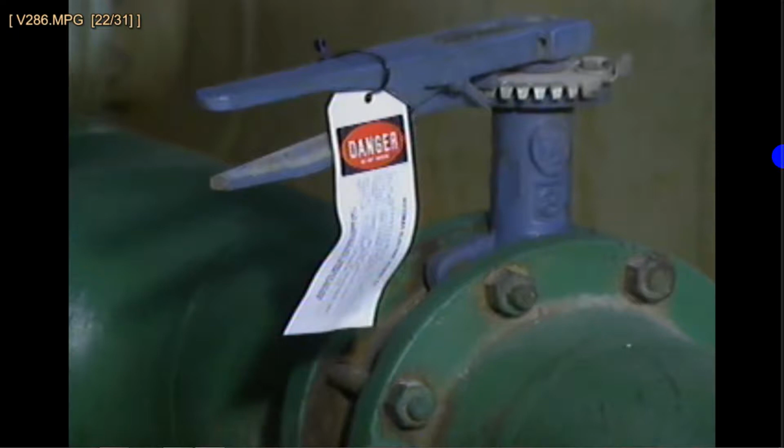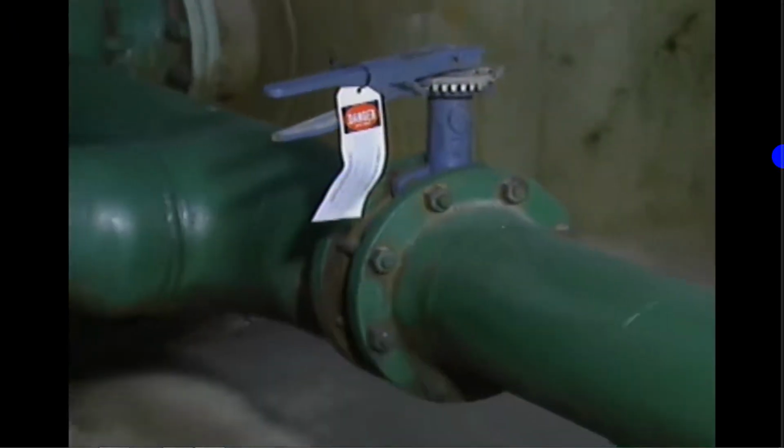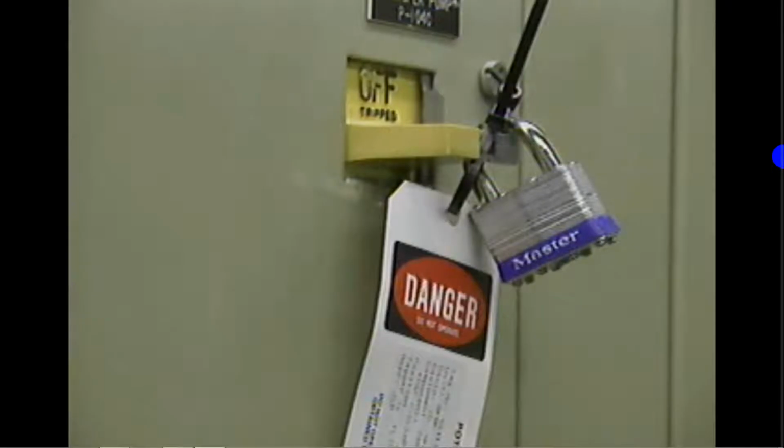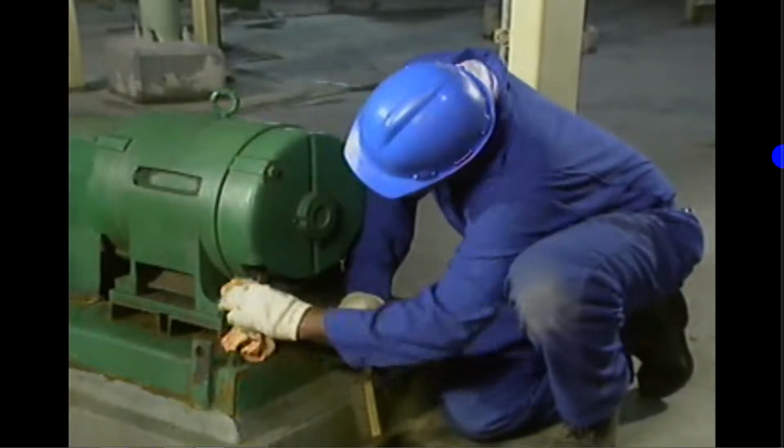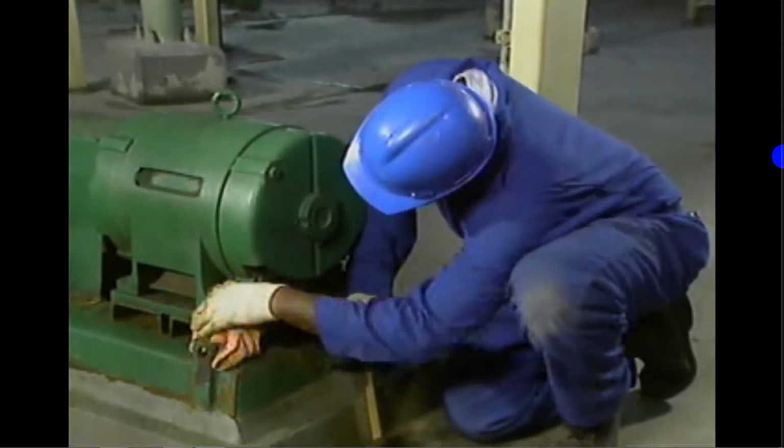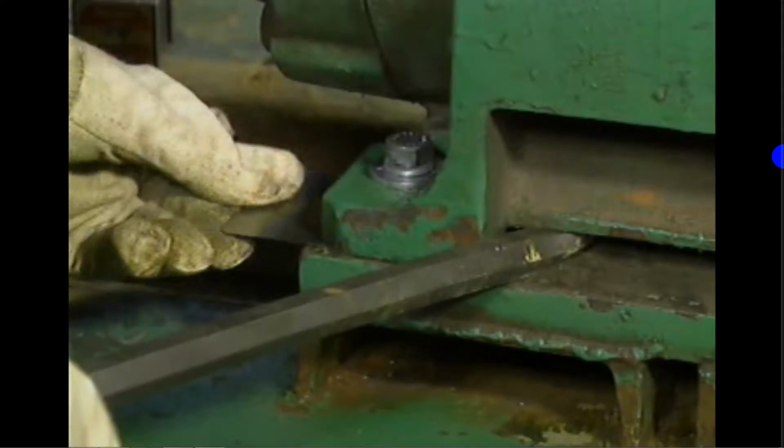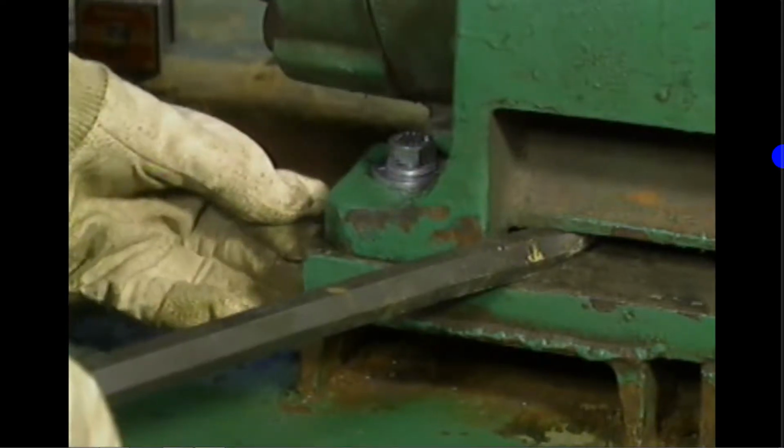The basic purpose of a shaft alignment is to make sure that the center lines of the shafts are as close as possible to being collinear, that is, that they form one continuous straight line. But before a shaft alignment is performed, certain preparations must be made. For example, since safety is always the top priority during any maintenance undertaking, all applicable lockout-tagout procedures must be followed. Also, the equipment being aligned must be cleaned and inspected, and any conditions that could interfere with the shaft alignment, such as soft foot, must be corrected.